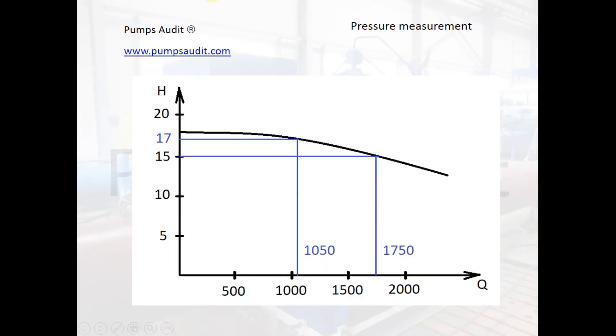This example illustrates how a relatively small difference in the pump head value can influence the flow value. A difference of two meters gives a difference in flow of 700 cubic meters per hour.